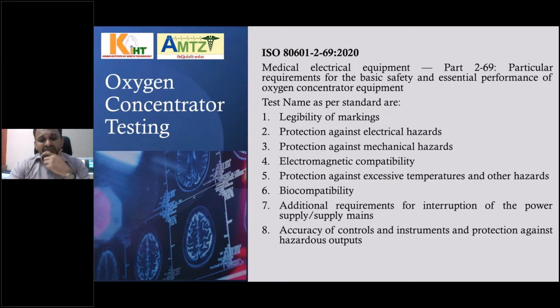Next is protection against mechanical hazards, as per 1-1. The mechanical tests include the ball pressure test, trapping zone, instability, overbalance, rough handling test, and acoustic energy on the mechanical part. For electromagnetic compatibility, there is the standard IEC 60601-1-2, which covers EMC as well. We conduct the radiated emission test and conducted emission test, and we also see the electrostatic discharge test and the surge test. These are commonly tested as per 2-69 for electromagnetic compatibility.